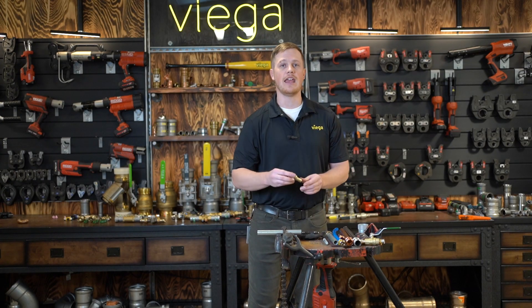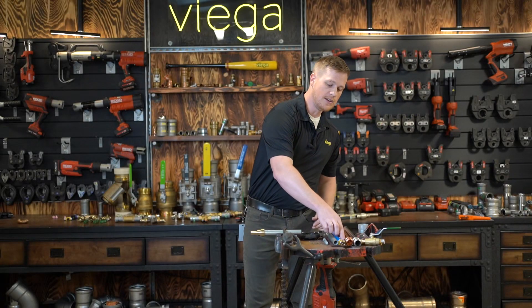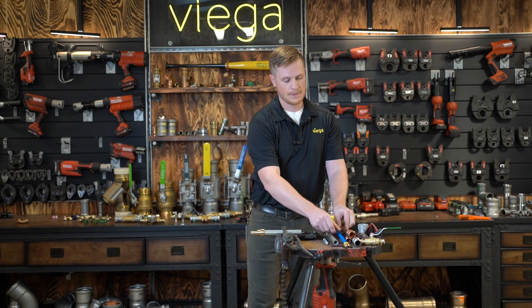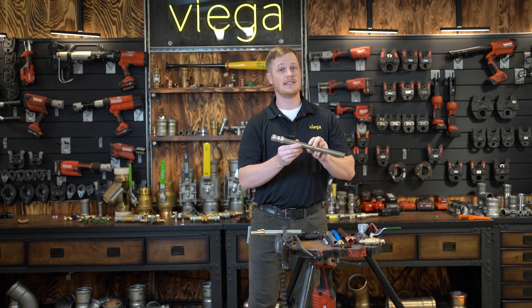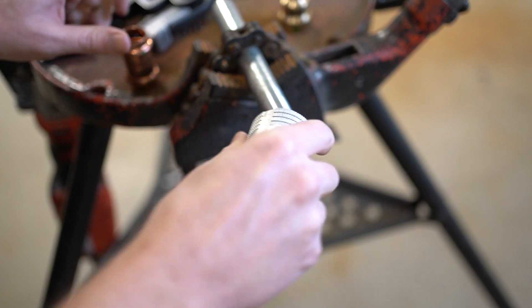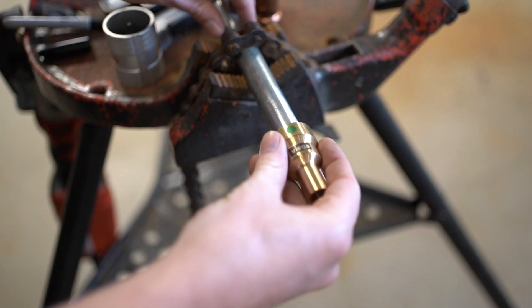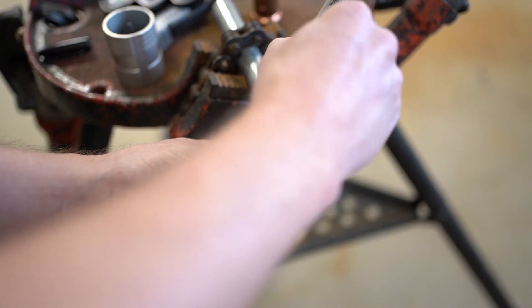In the field, we've all encountered galvanized water pipe that needs to be repaired or replaced. At Viega, we have introduced a bronze fitting to go from iron pipe size galvanized to copper tubing size. This can be used on copper pipe, stainless steel pipe, or even PEX. We do not connect galvanized pipe directly to copper due to galvanic corrosion. With Viega's bronze transition adapter, we can go from iron pipe size to copper tubing size.